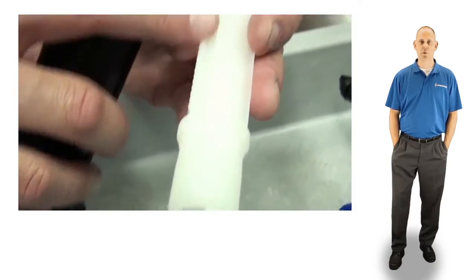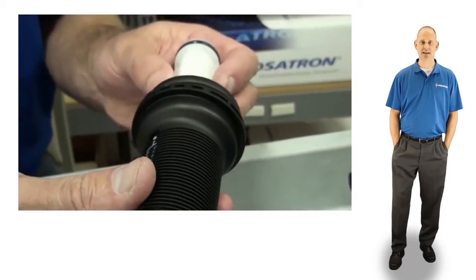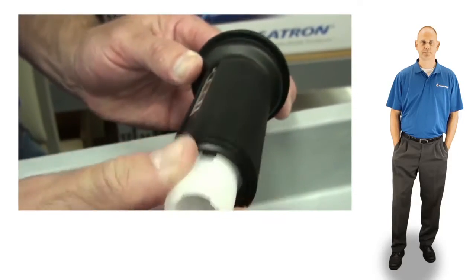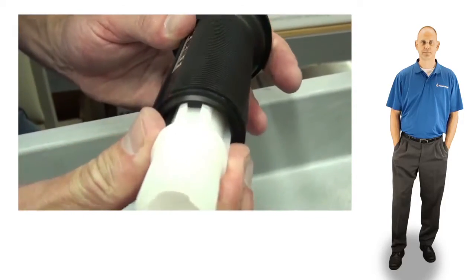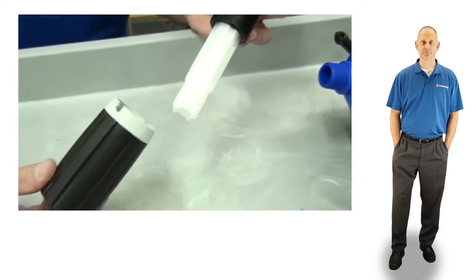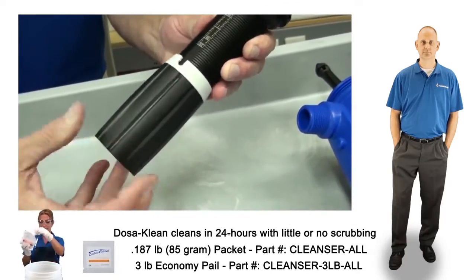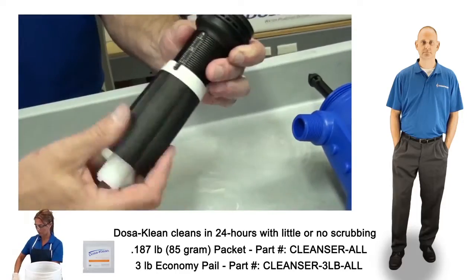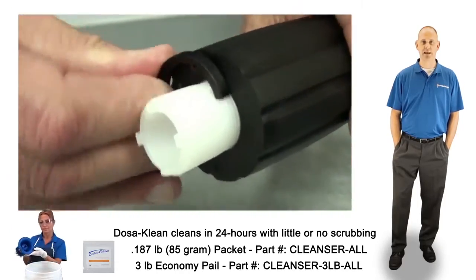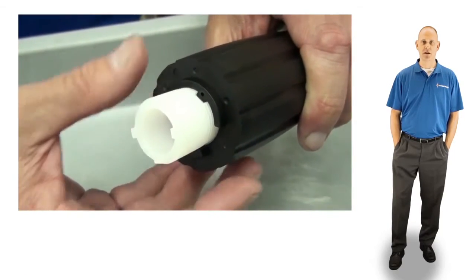Next, align the groove in the white stem with the tooth inside the lower portion of the black sleeve and slide the stem down in as far as possible. Replace the C-clip by sliding it over the threads. Rotate it until it clicks into place and then thread on the lock nut and hand tighten.